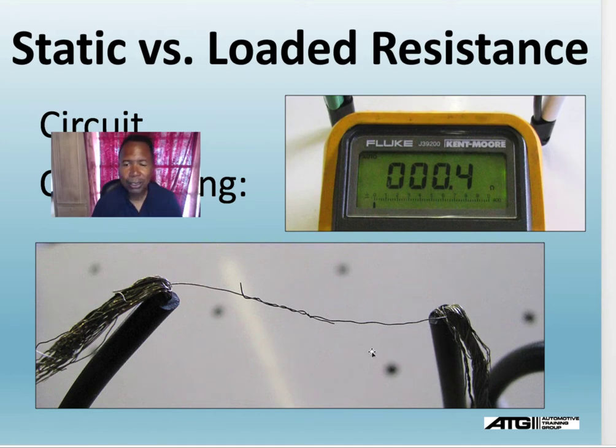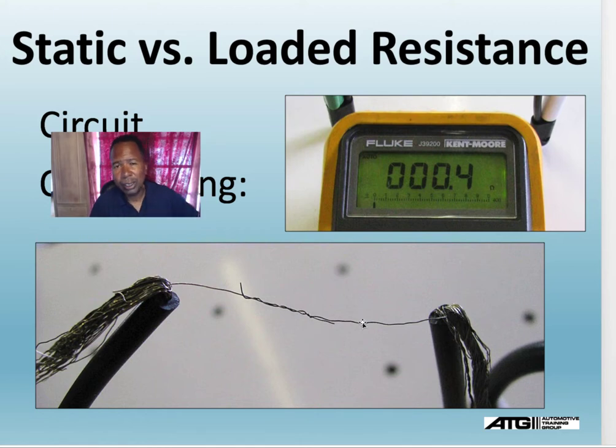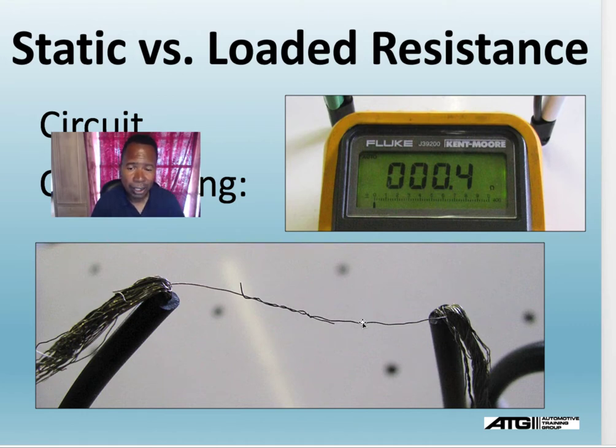If I use an ohmmeter, like you see here, to check this connection on this wire, it would read good. It will tell you nothing is wrong with this wire. But a voltage drop across this wire will tell you the wire was bad, because when current is supposed to flow through all of it and is only flowing through part of it, you're going to have a high voltage drop.